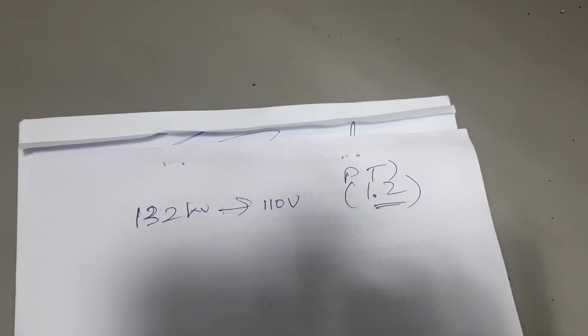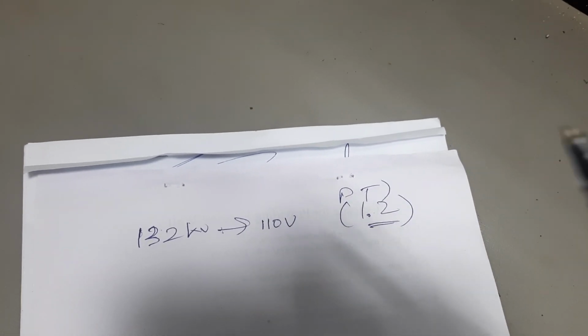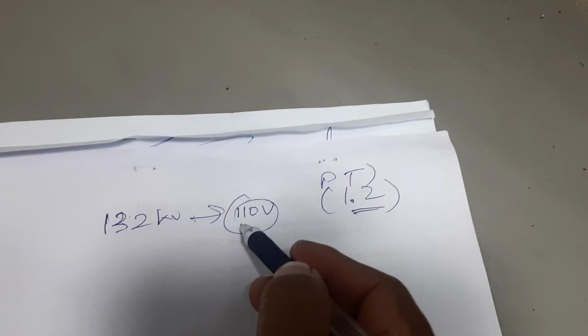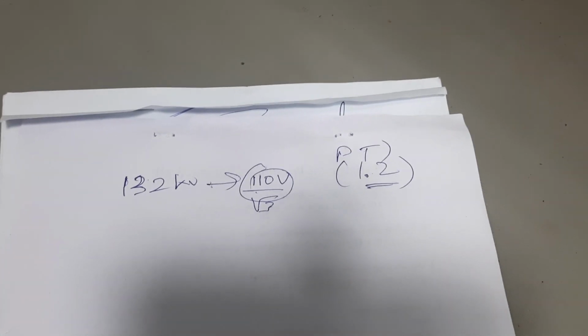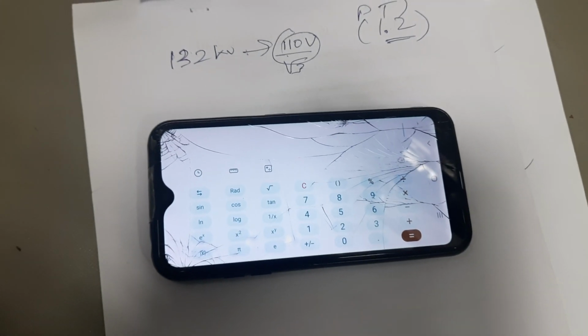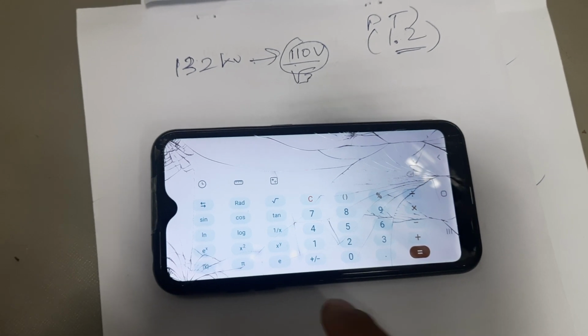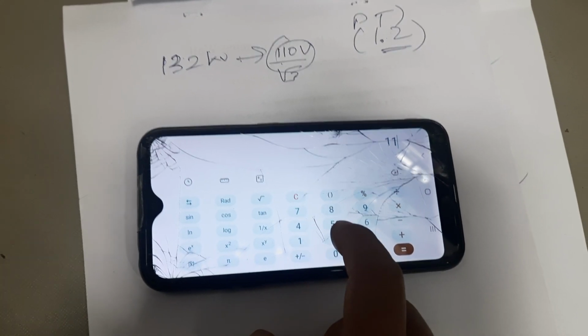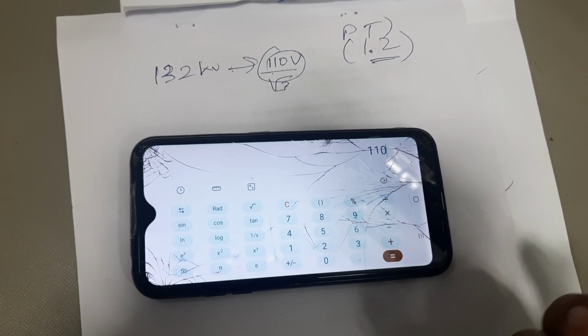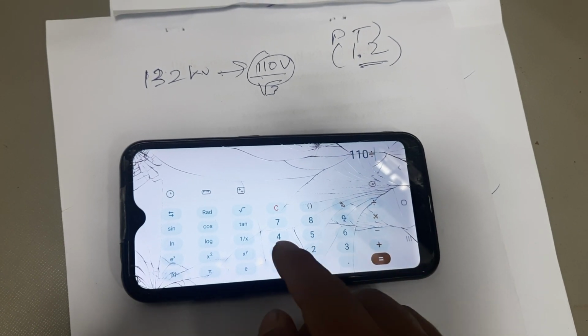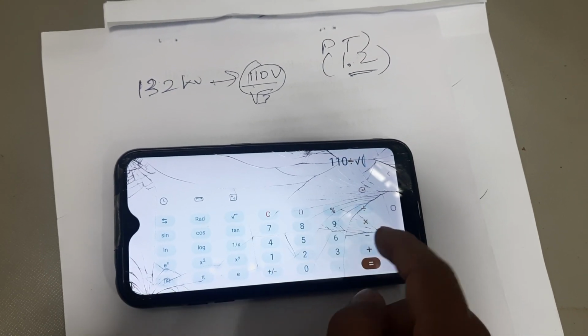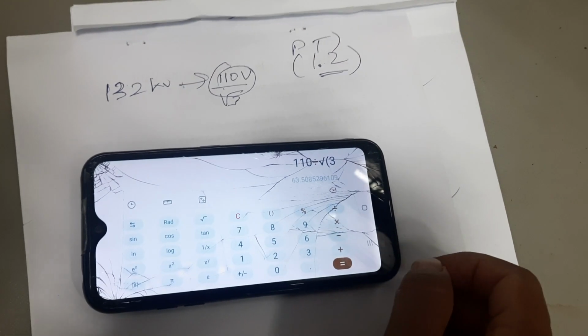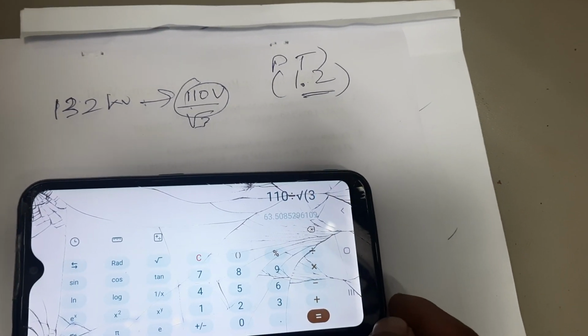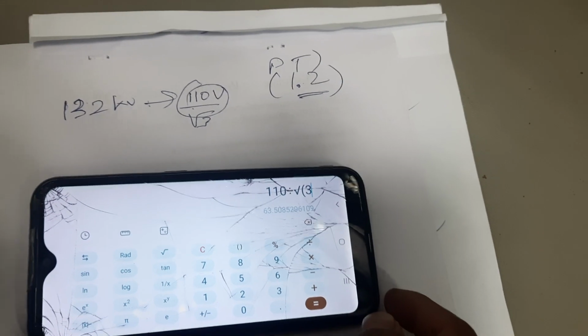We can take the phase to phase also, but we will be taking only the phase to earth. 110 is the phase to phase, and phase to earth will be divided by √3. Let me take a calculator. Your meter secondary should record a phase to earth voltage of around 63.5 volt.